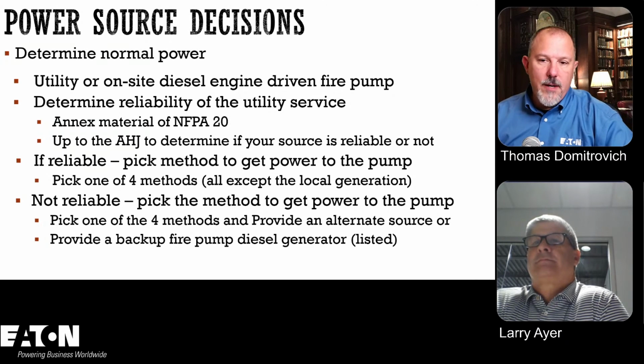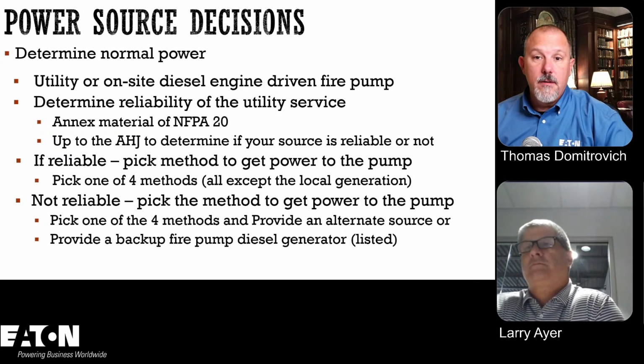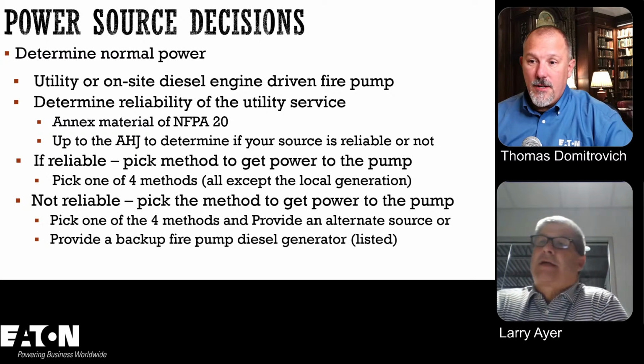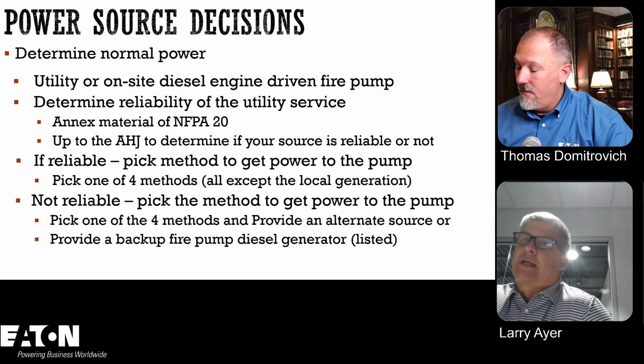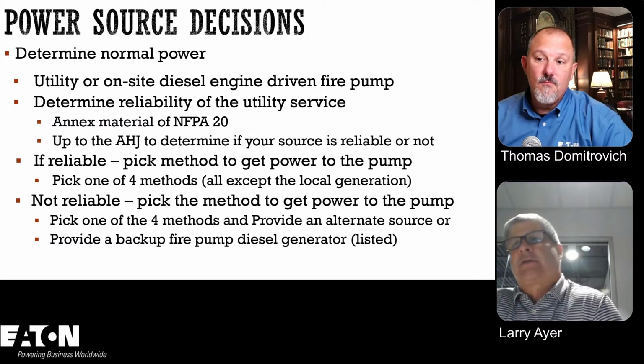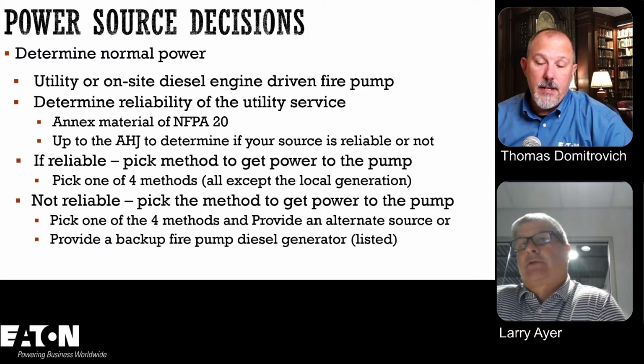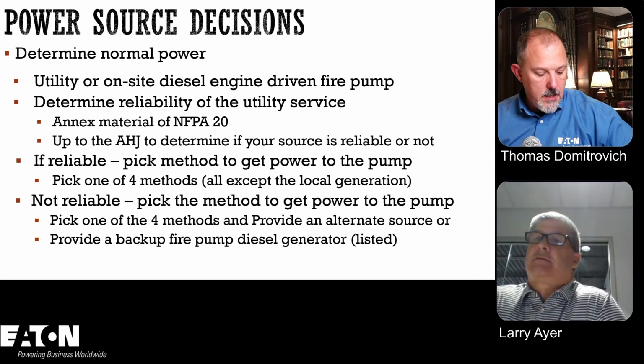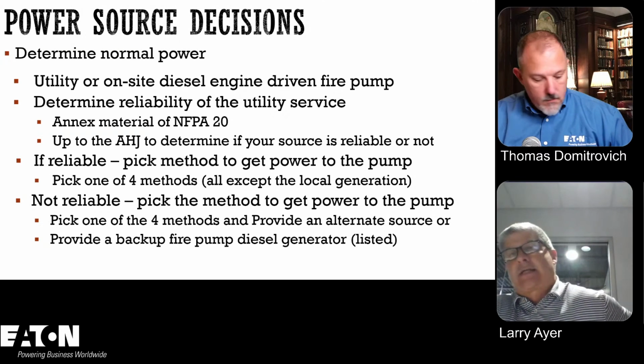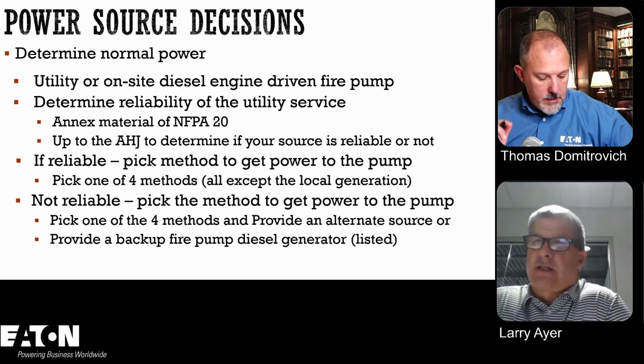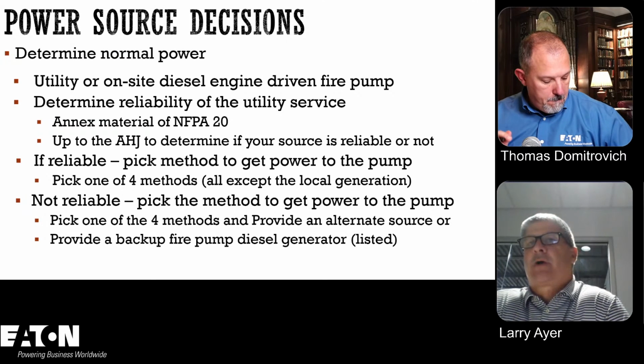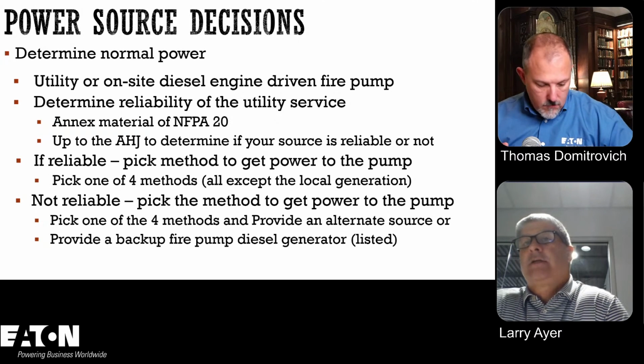If I have to do an alternate source, why wouldn't I just always pick a diesel-powered fire pump? I think it depends on how your building's laid out. Where is your electric service in relation to your water service coming into the building? Are you in a downtown building, and do you have to worry about putting that diesel pump inside the building, and about exhaust and ventilation and things of that nature? You need to probably have stored fuel on there. You typically need an 8-hour fuel supply for these devices.